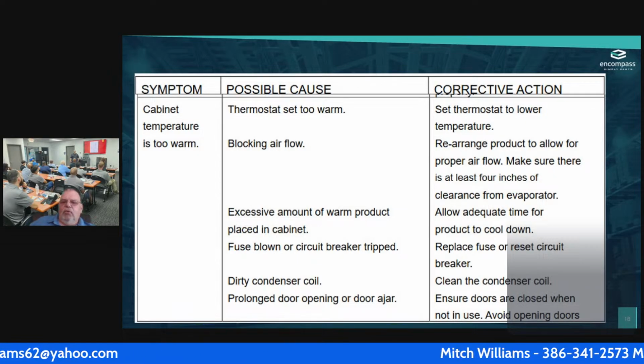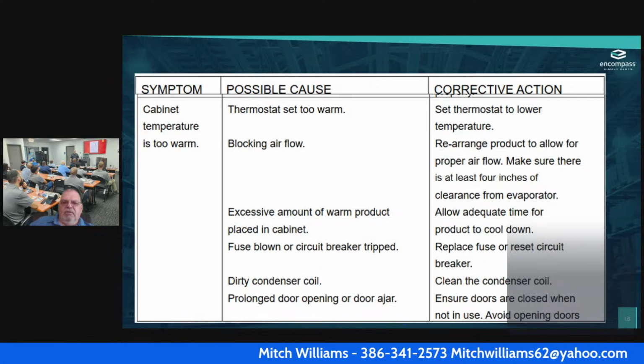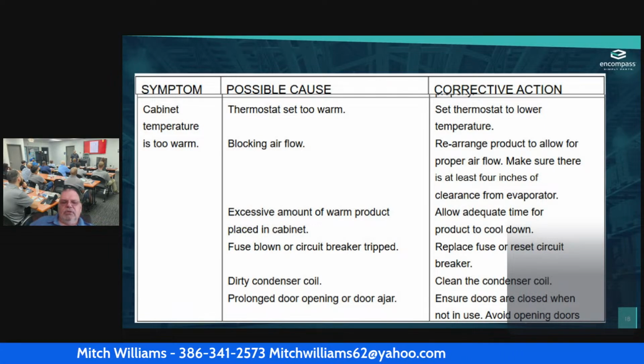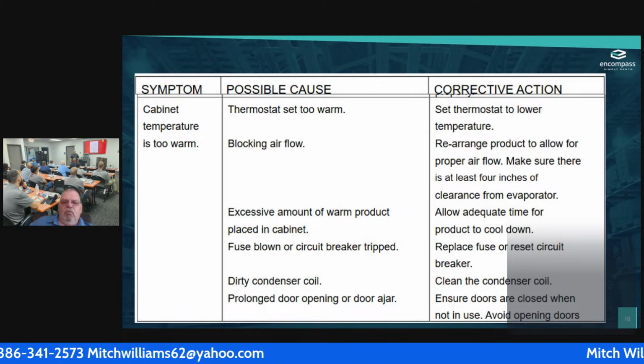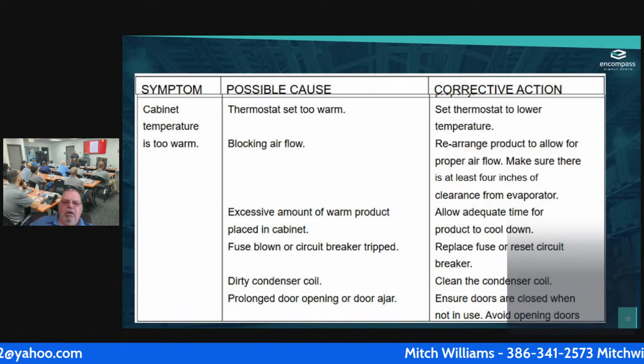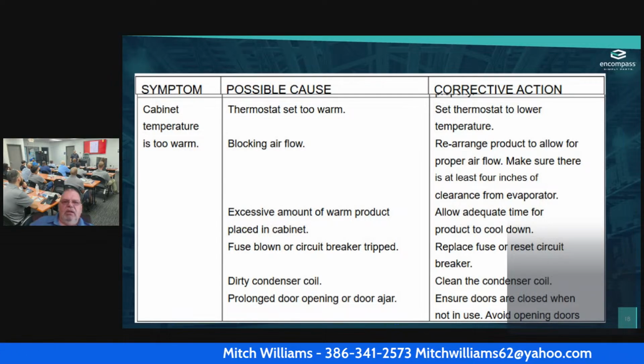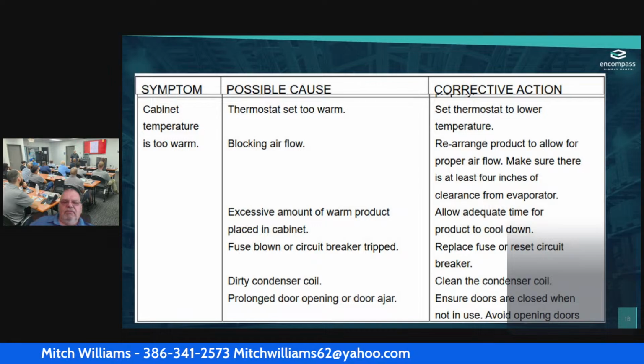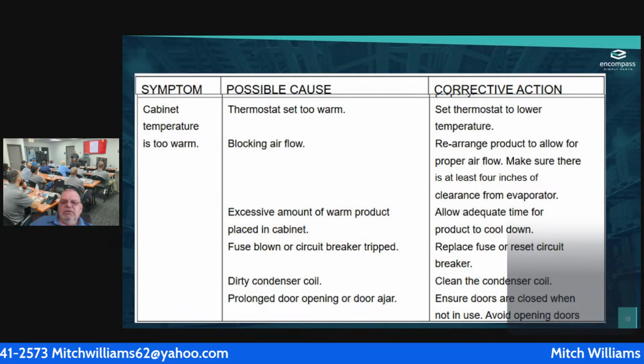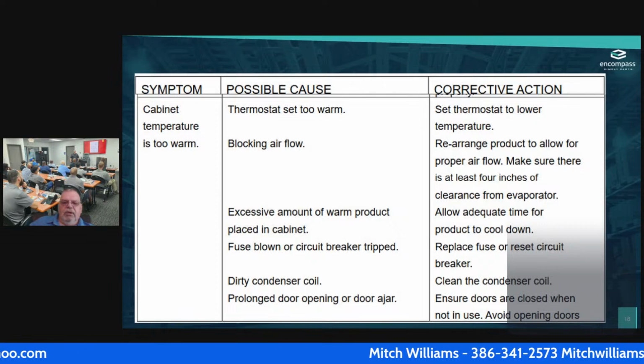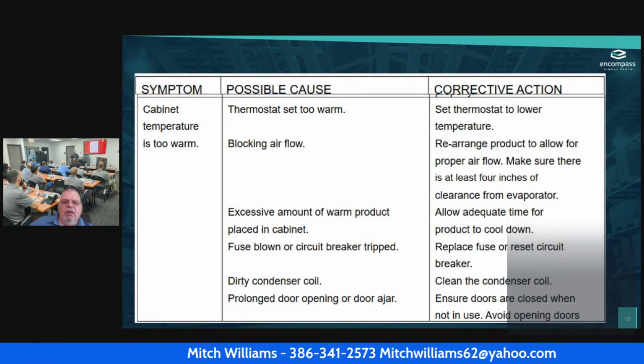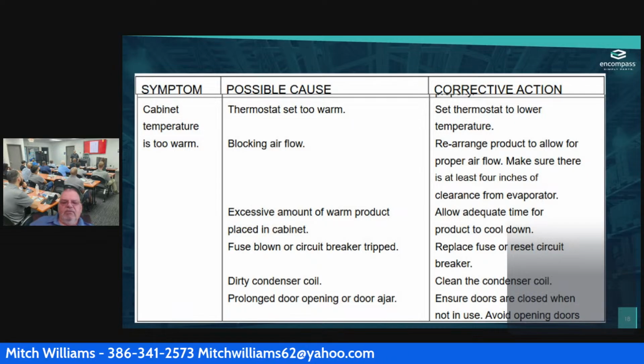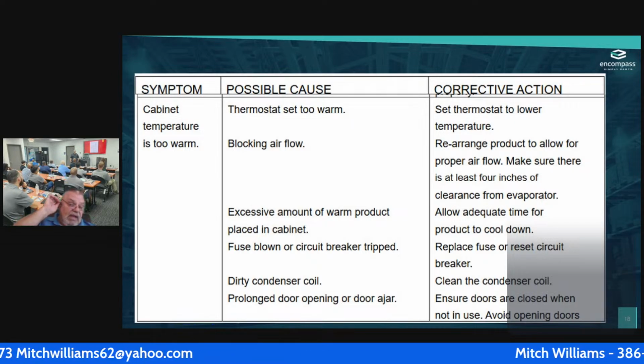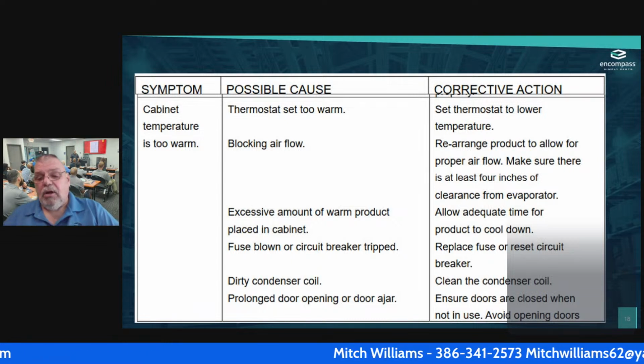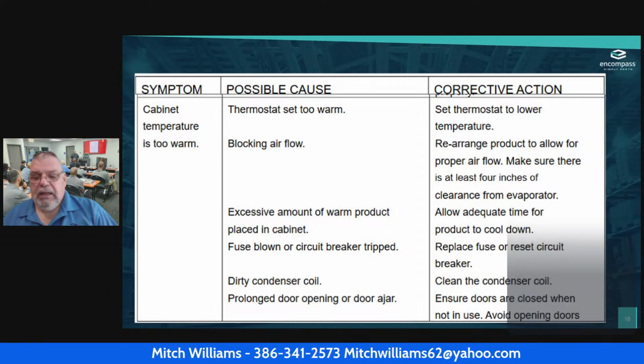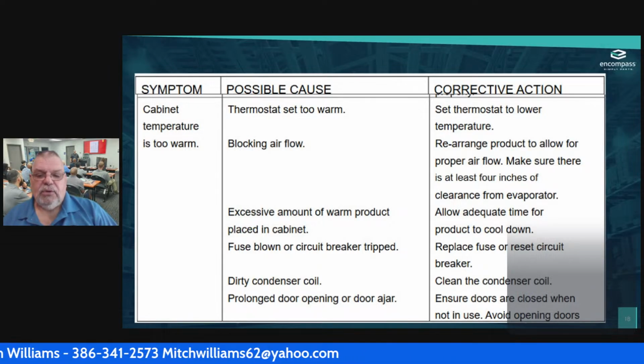Make sure that there are at least 4 inches of clearance from the evaporator and the condenser coil. Then, an excessive amount of warm product has been placed in the cabinet. That could be my problem. Then of course you just have to allow for the unit to cool down. Could be the fuse or the circuit breaker is tripped. So I'm going to need to either replace the fuse or check the circuit breaker and untrip it. It could be that the condensing coil is dirty. If that's the case, of course, you just need to clean the condensing coil. If I have prolonged door openings or the door is ajar all the time, that's going to be my problem. And I'm going to have to just tell the people that they have to allow time for it to recool back down.